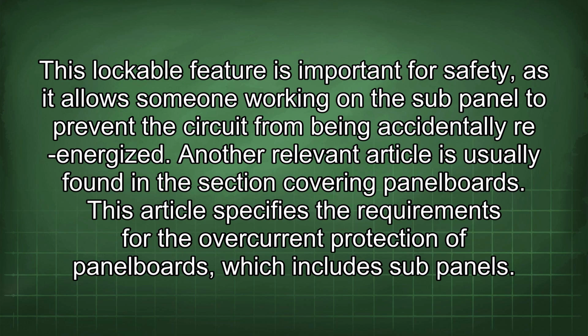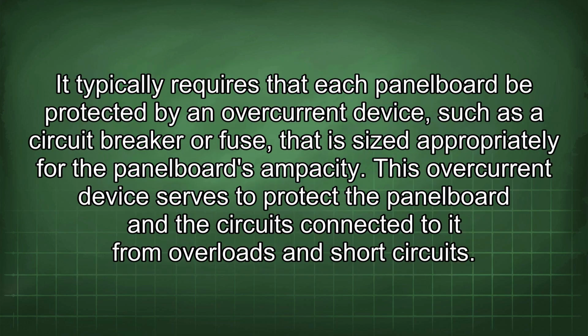Another relevant article is usually found in the section covering panelboards. This article specifies the requirements for the overcurrent protection of panelboards, which includes sub-panels. It typically requires that each panelboard be protected by an overcurrent device such as a circuit breaker or fuse that is sized appropriately for the panelboard's ampacity. This overcurrent device serves to protect the panelboard and the circuits connected to it from overloads and short circuits.